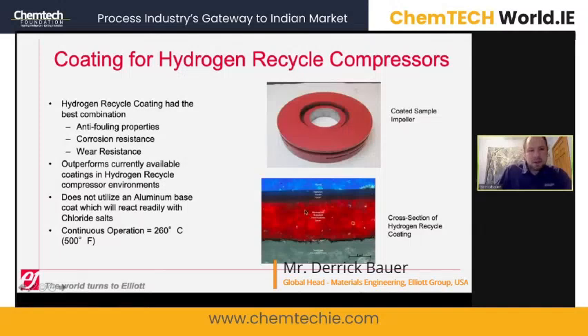So the cross-section of the coating that is useful for hydrogen recycle service is shown here, whereas basically a permeation resistant intermediate layer along with the non-stick top layer is applied. This coating is utilized up to 260 degrees Celsius, which is normally well beyond the maximum temperature that hydrogen recycle coatings would see during service. And again, this was a coating specifically for ammonium chloride deposits, which the industry standard coatings have not really looked at, that application.